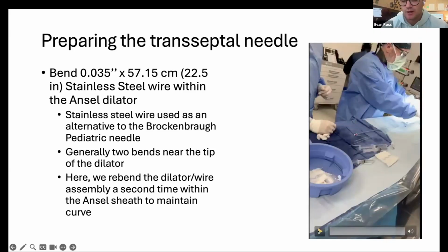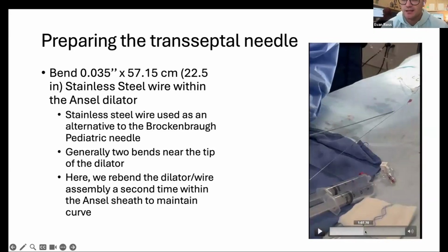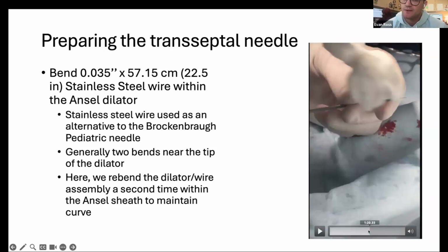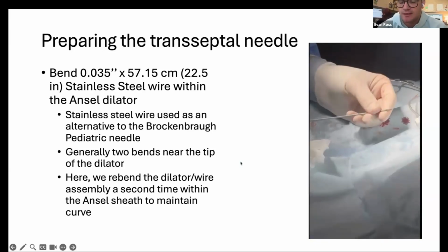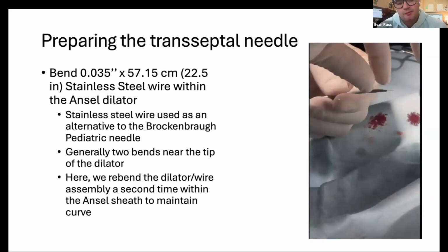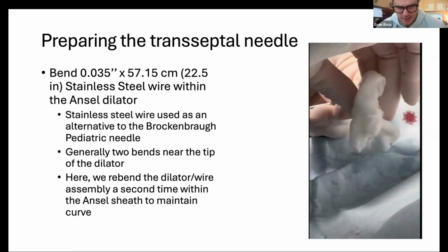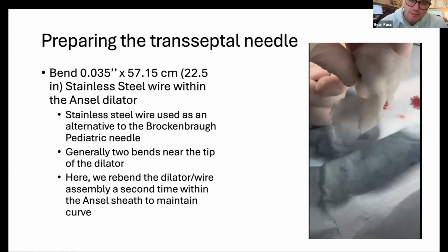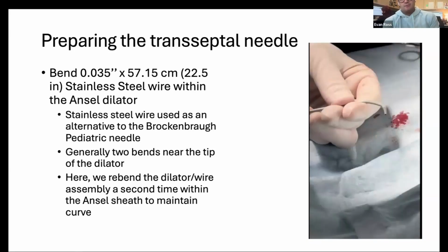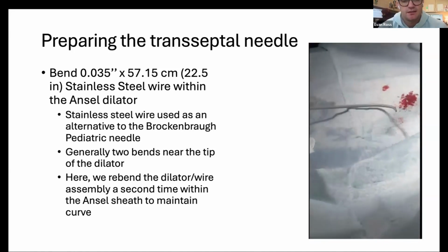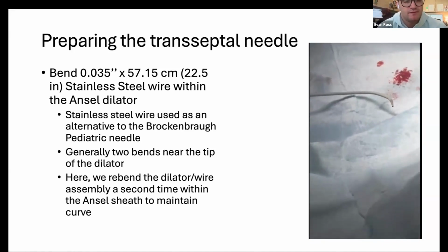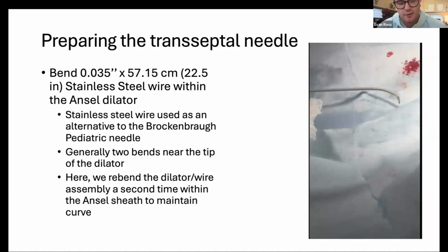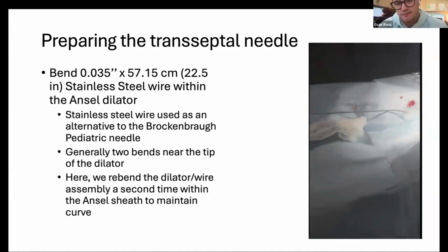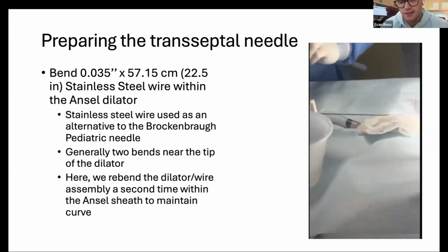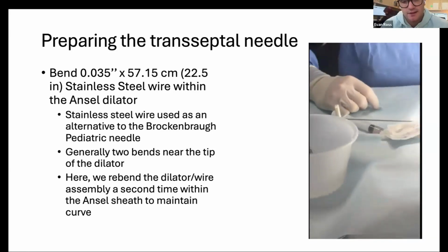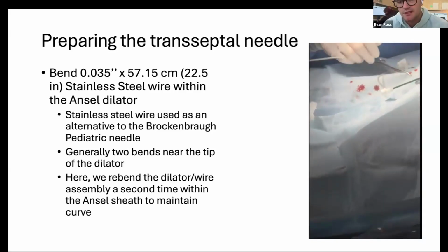I have a little video attached, and we'll walk through how we bend the needle. I think that's often a question that people have, but you can see basically our standard will be to make 2 bends at the tip. The pediatric Brockenbrough needle was standard. Those went on back order. They may be available from another company now, but we are now using a medical stainless steel wire that's cut to 57.1 centimeters. It's 22.5 inches, which works really well. It's very bendable, and it's very stiff and allows for pretty good handling. And you'll see the system that we use. It's just an alternative, very inexpensive, and we can provide that information as well.